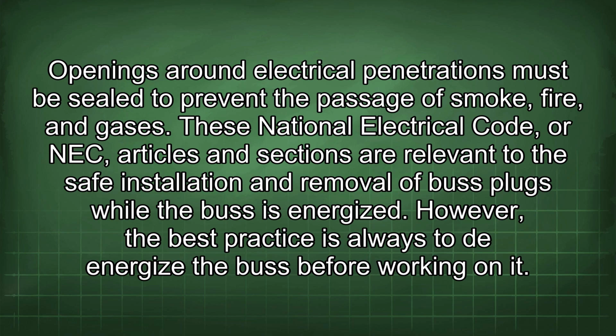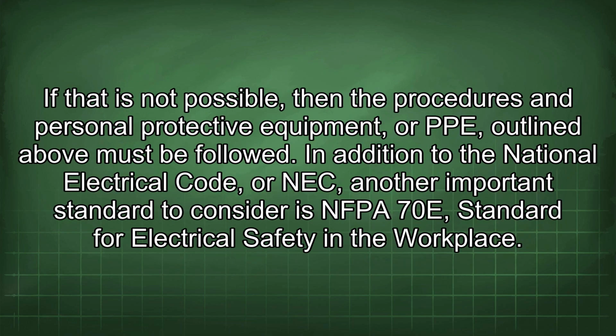These National Electrical Code, or NEC, articles and sections are relevant to the safe installation and removal of bus plugs while the bus is energized. However, the best practice is always to de-energize the bus before working on it. If that is not possible, then the procedures and personal protective equipment, or PPE, outlined above must be followed.